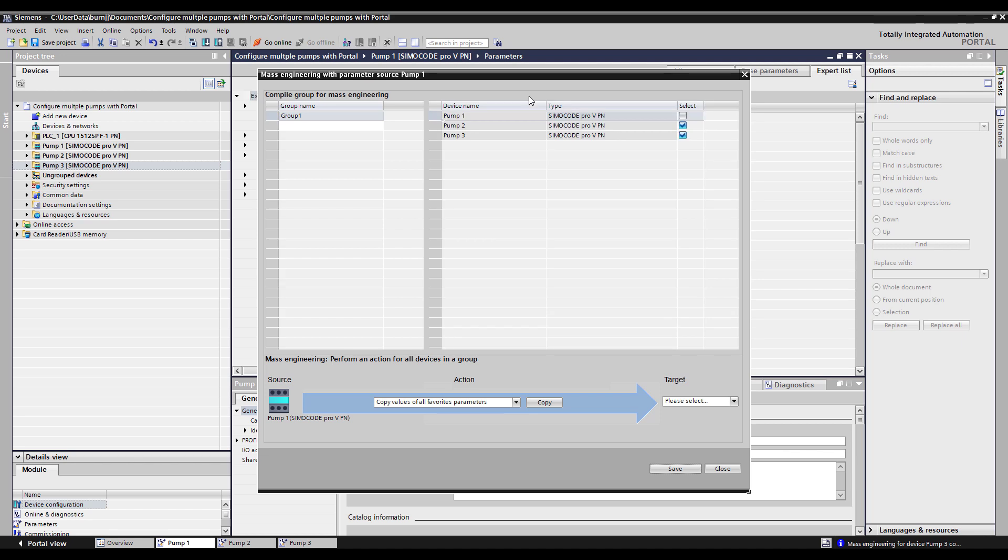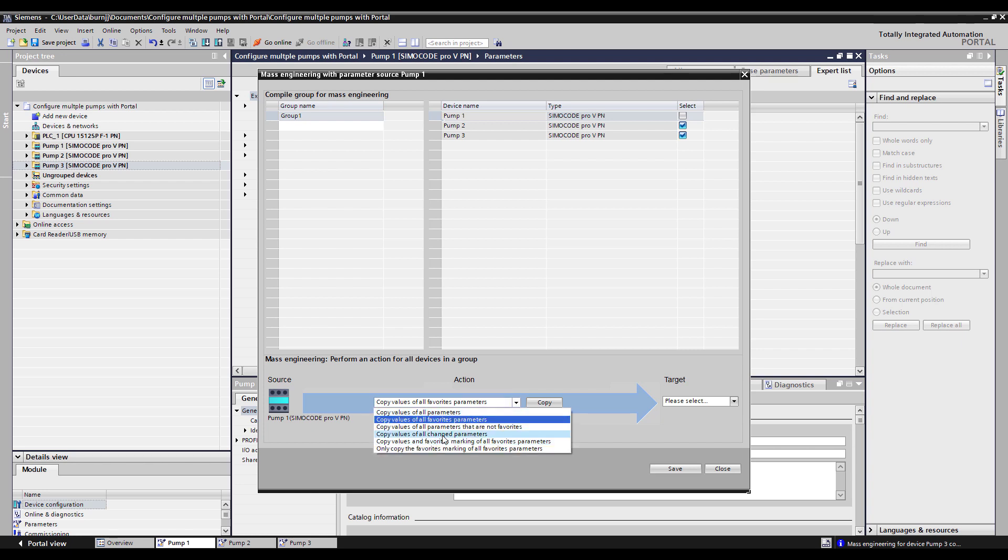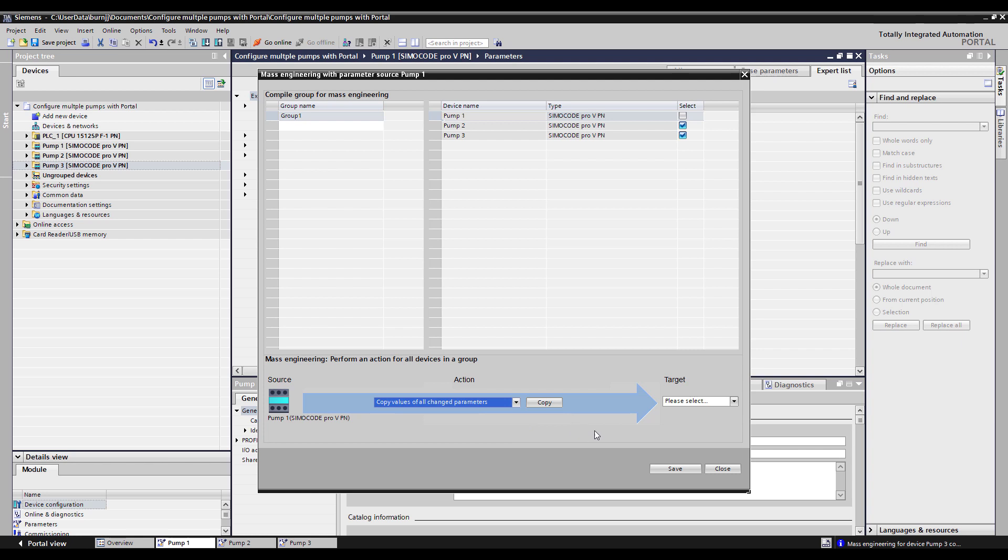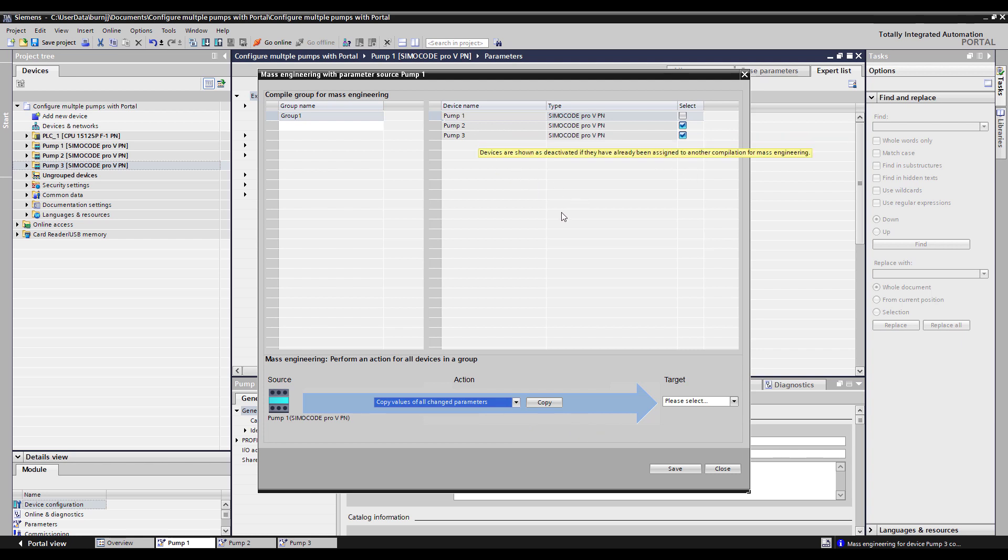We click on Mass Engineering. It has a source file which is how you got in here, which was through the parameter page for pump one. So pump one is now defined to be the source file. What do you want to change? We want to copy all the parameters that have been changed. And where do we want to copy them to? We want to copy them to pumps two and pumps three, and we do that via groups.